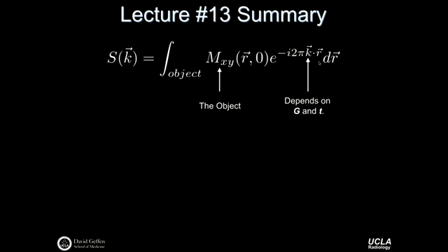We saw these plots of these wave functions over space. Then the k value itself is going to depend on the gradient, and the gradient is a function of time, so it inherently depends on time as well. At the end of the day, we don't care too much about what the actual gradients are or exactly what point in time we are. We just care about the k vector, or the k point, that we're trying to acquire. It's the gradients that will move us around to different k points. We'll talk about this more today, but gradients will move us around so we can acquire those different k points, get a spatial frequency weighting of our underlying object, integrate that into our coil so that we have a received magnitude of the presence or absence of that particular spatial frequency.